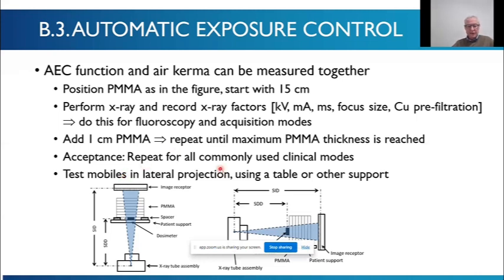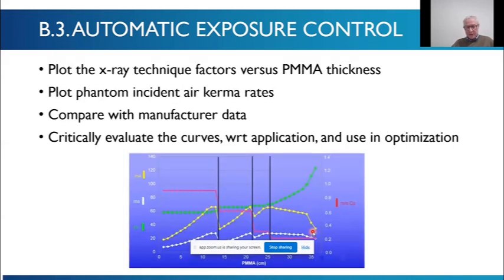And then do this for all the commonly used clinical modes for a standard field of view, like Annalisa suggested. So like maybe 20, 25 centimeters, or even 40 or 42 centimeters for large, like body DSA, for example. You might want to test mobiles in the lateral projection because you can't put all the PMMA on the detector itself. You have to support it in some sense. You may not have an appropriate couch, an X-ray couch, so you may find a table and support it laterally for lighter mobiles. And then once you've acquired your data, you need to plot the technique factors as a function of PMMA thickness and critically examine what's going on with the system.